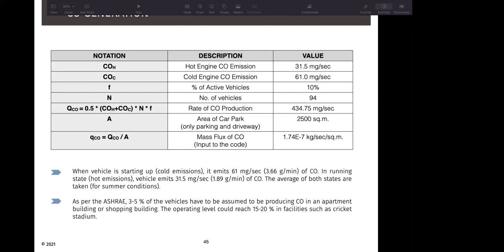For the CO simulation, we would even need to calculate the CO flux into the system. This data can be found in the ISHRAE handbook, where you can calculate the CO flux in a system. The hot engine emission and the cold engine emission, the average of both is taken for 10% active cars. So in this case, for 94 vehicles, we take 10% active vehicles and we calculate the rate of CO production and divide that by the area of car park, which will give us the mass flux of CO. That becomes the input into the code, your boundary condition for CO. ASHRAE even suggests that for buildings such as stadiums, we can take the operating level to be around 15 to 20%.